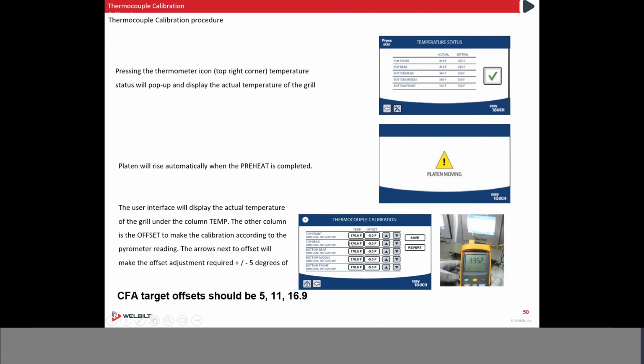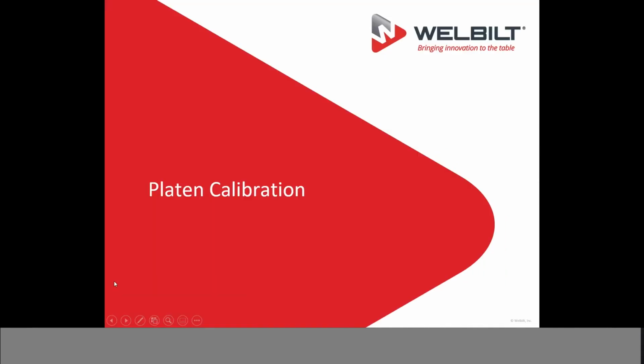So get it to as close as possible to what your meter is saying, and then look at the offset. Are we close to 5? Are we close to 11? Are we close to 16.9? And just move it to whatever those locations are. That's your thermocouple calibrations. Little different, process is still the same.